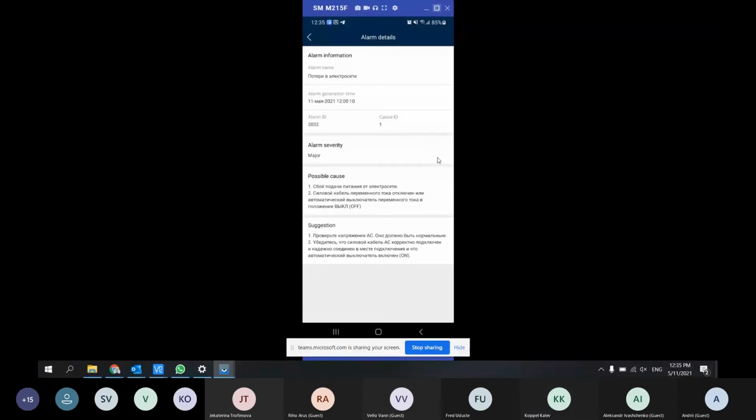So there is a voltage on the AC side, but the inverter doesn't see this voltage. So in this case, together with the log, support will check the log, see that the inverter shows 0 voltage, but you show that this voltage is not actually 0. So in this case, it will be enough to approve the warranty replacement.